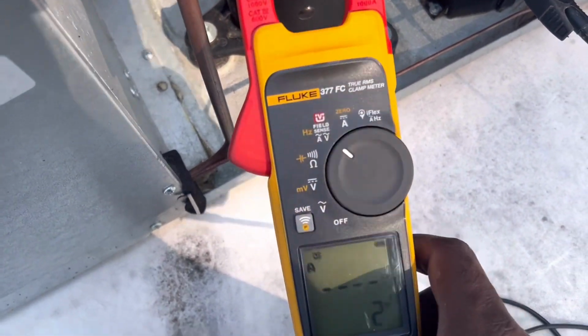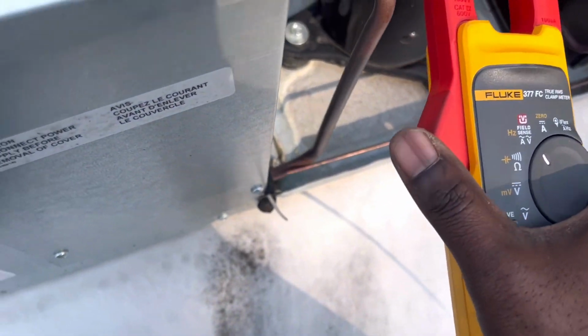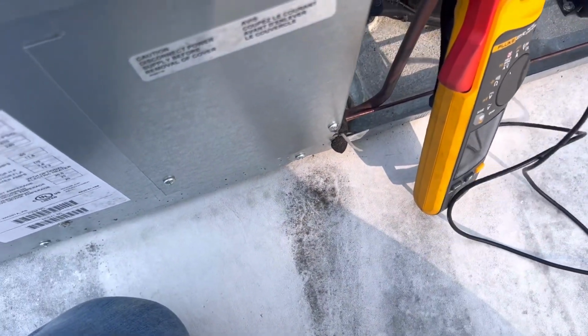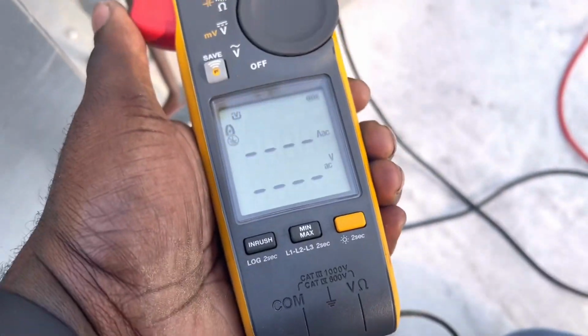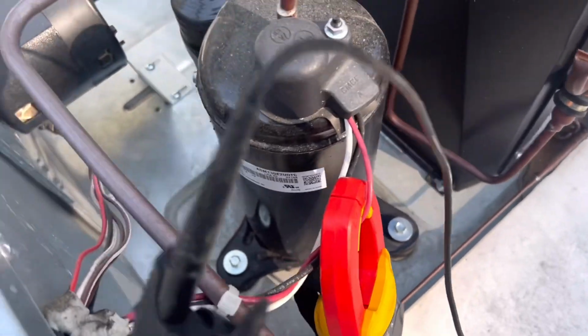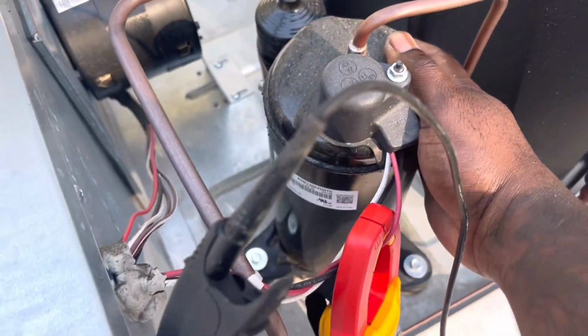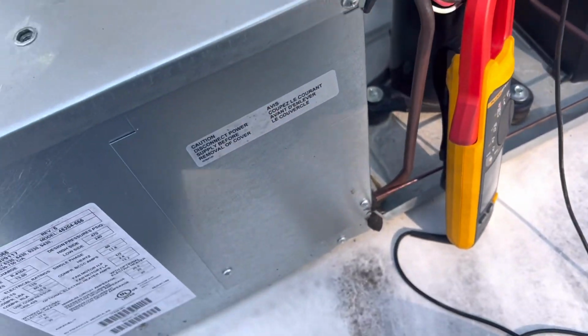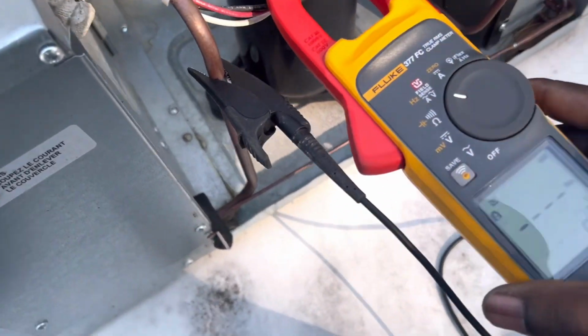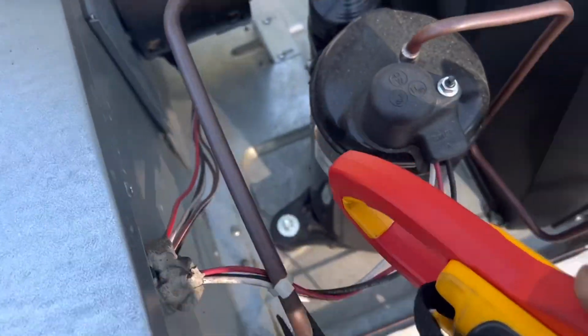My amp clamp has to be grounded to get the voltage measurements. My compressor is not running at all. It's not even hot. So I'm definitely going to be taking a look at the capacitors. This should be a good ground. Now I know the fan is moving, so let's grab something from the fan and see if we can get a reading on that.